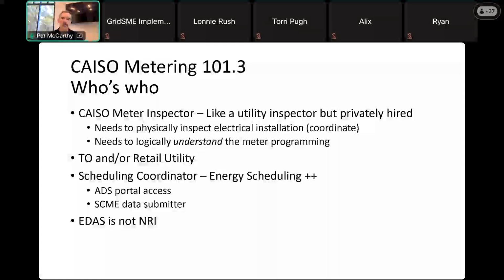So if you had a procurement issue and changed your CT ratio, or decided that based on some updates to your PPA you're going to move a CT location somewhere, that CAISO inspection is going to fail. And what that really means is you're going to need to update and get approved schematics that match what you've built, so that the CAISO inspector can say, yep, what's on the drawing is what's in the yard.